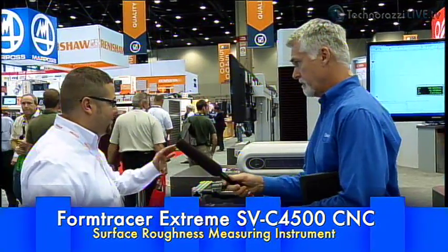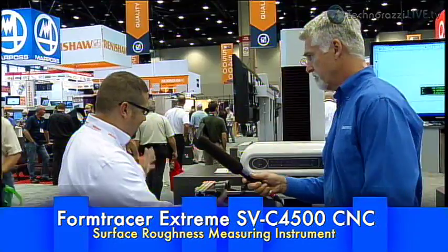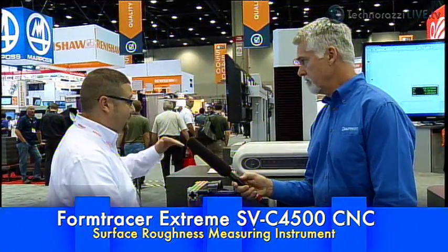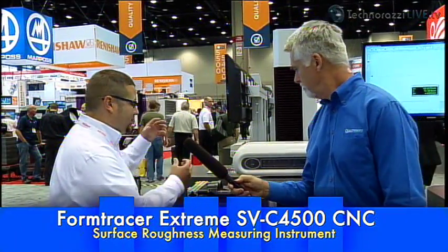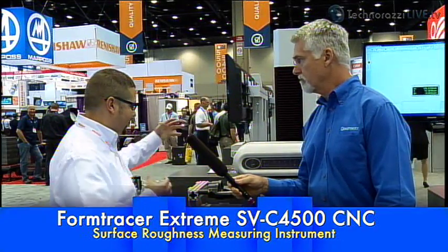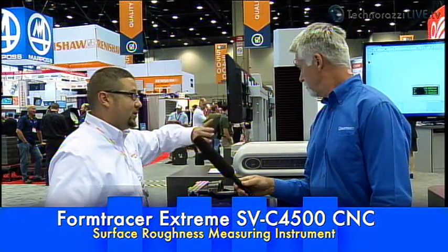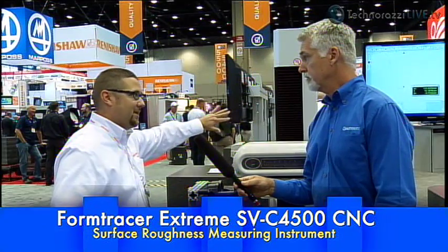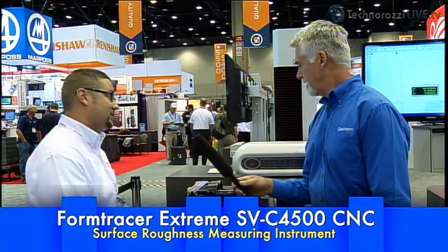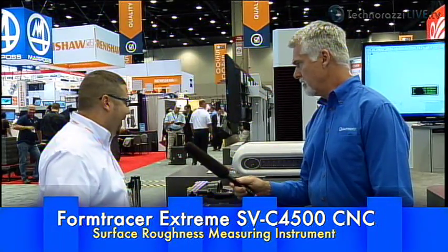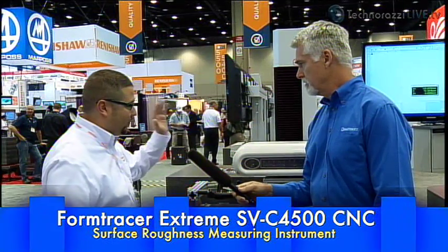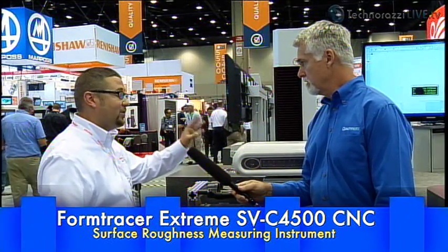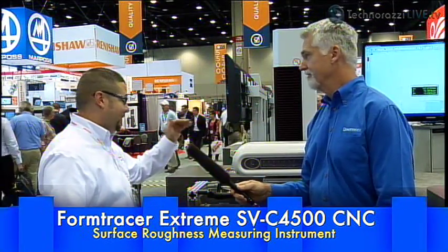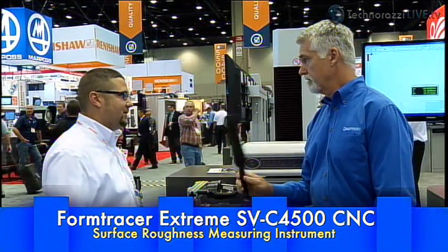No, absolutely. We have different models of this. We have different size columns, bases. We also have a big brother to this, so that if we have much larger parts, thinking aircraft, automotive, things that are heavier and need more room, we have a version of this where the column will move, much like on a CMM, and it's still a measuring axis at that point. And accuracy? Well, the resolution on this is sub-micron. I think it's 0.02 micron on here, and the accuracy relative to the measurement, we're talking just a few microns.